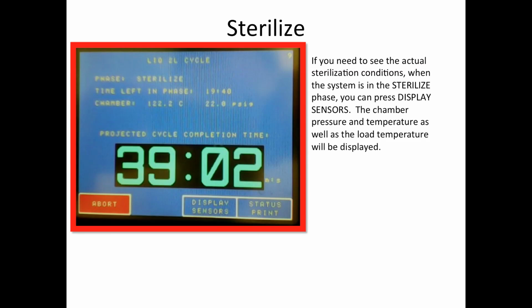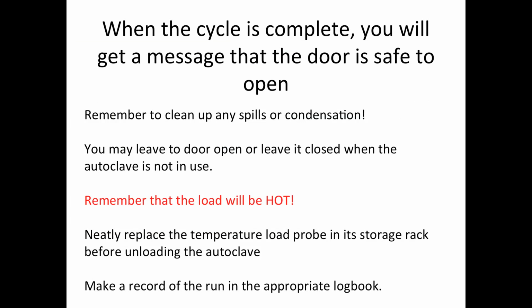Now, if you need to record or to observe the actual sterilization conditions when the cycle is in the sterilize phase, you can press the Display Sensors button. The chamber pressure and temperature as well as the load temperature will be displayed. And when the cycle is complete, you will get a message that the door is safe to open.